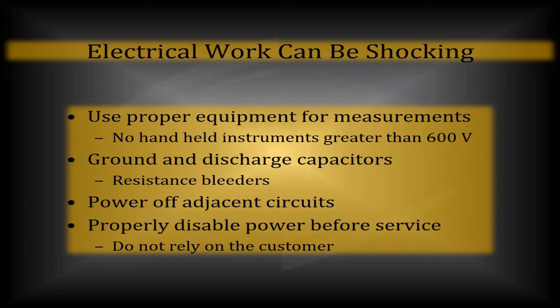magnetic field can also do what's called inducing power, inducing voltage onto the other wires even though they're not powered up at all. So we've seen that for years with cable wires. People run regular power wires with their cable wires across a ceiling or through an attic. They strap them together to make it look nice. Well, in reality, even though the cable wire doesn't have power on it, it gets power onto it and it ends up messing up the TV or the cable box because of that induced voltage that is on that power line. So make sure you're taking care of yourself by shutting off any adjacent circuits.